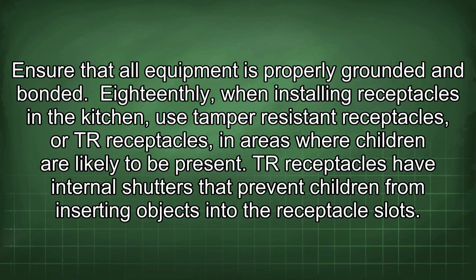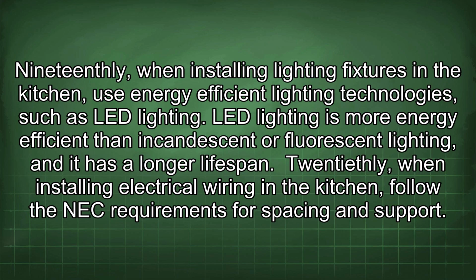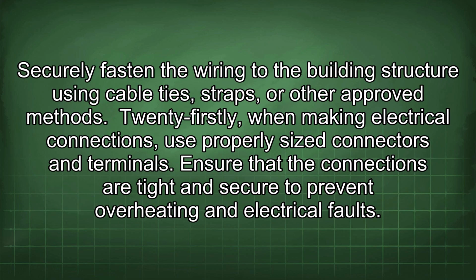18thly, when installing receptacles in the kitchen, use tamper-resistant receptacles, or TR receptacles, in areas where children are likely to be present. TR receptacles have internal shutters that prevent children from inserting objects into the receptacle slots. 19thly, when installing lighting fixtures in the kitchen, use energy-efficient lighting technologies, such as LED lighting. LED lighting is more energy efficient than incandescent or fluorescent lighting, and it has a longer lifespan. 20thly, when installing electrical wiring in the kitchen, follow the NEC requirements for spacing and support. Securely fasten the wiring to the building structure using cable ties, straps, or other approved methods.